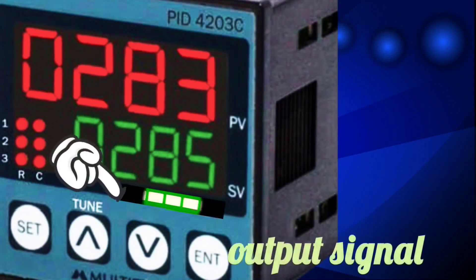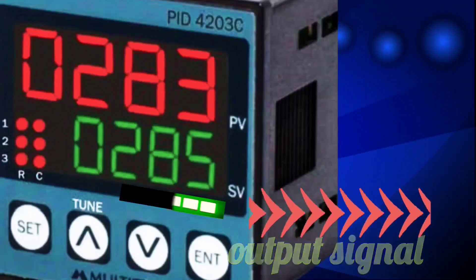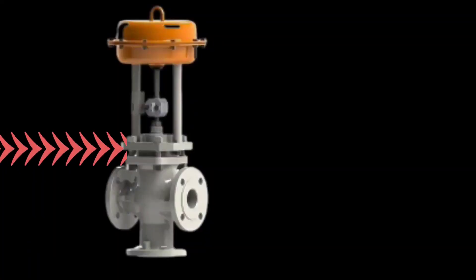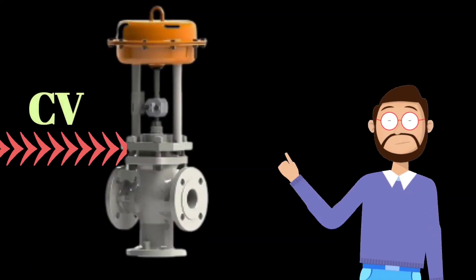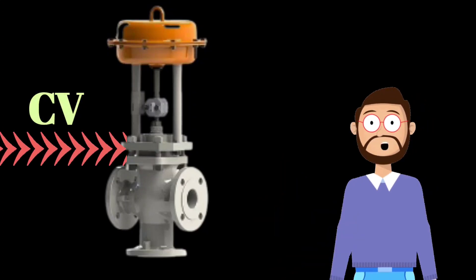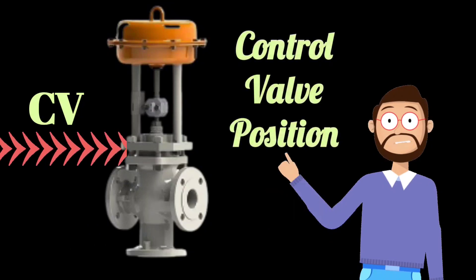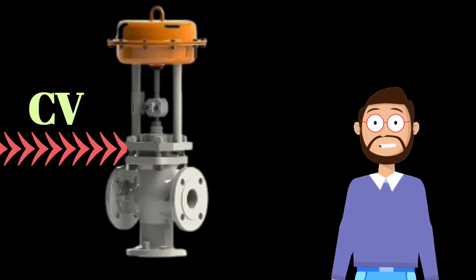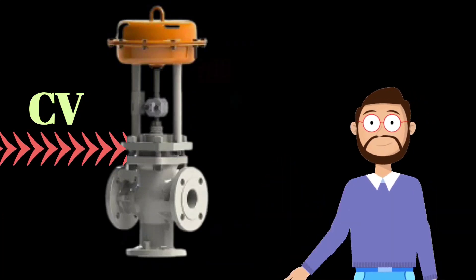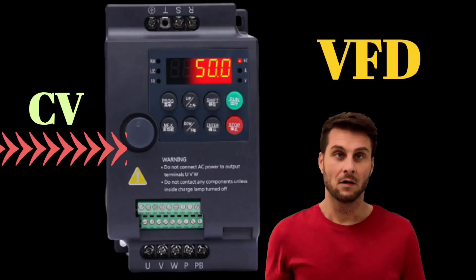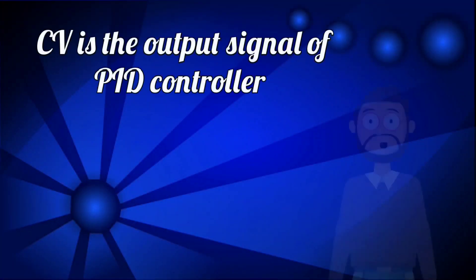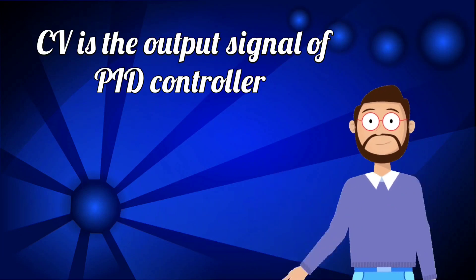To reduce the error, an output signal is sent from the PID controller. This is called the control variable, or CV. Because this output is normally sent to a control valve, some people also call it the position of the control valve. The control variable signal is sent to a control valve or a variable frequency drive, which means VFD. CV is the output signal of the PID controller, which is sent to minimize the error.